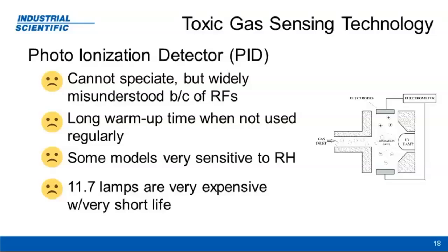One thing that's widely misunderstood about PIDs is that if they're not used very often, if they're used sporadically, they have a long warm-up time. The lamp has to warm up and burn in. If you don't understand that, and you don't use it all the time, you spend half your morning chasing the baseline on the lamp while it warms up.